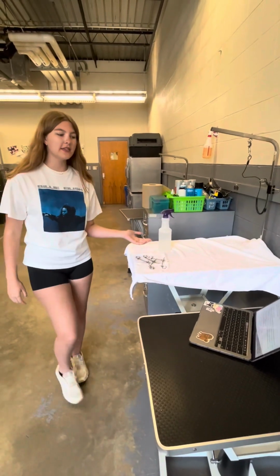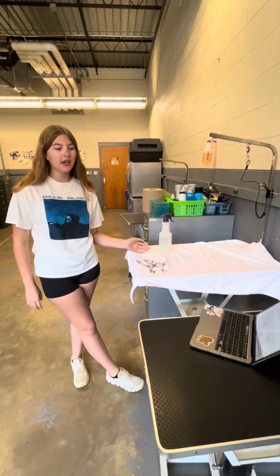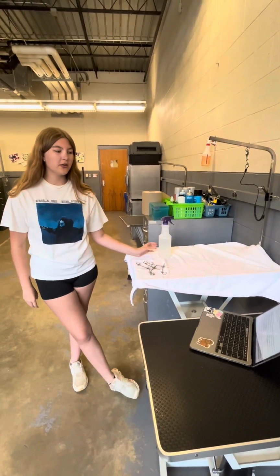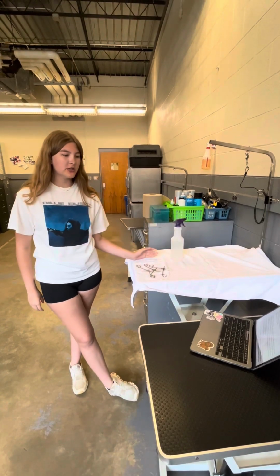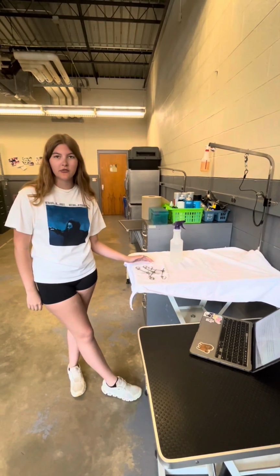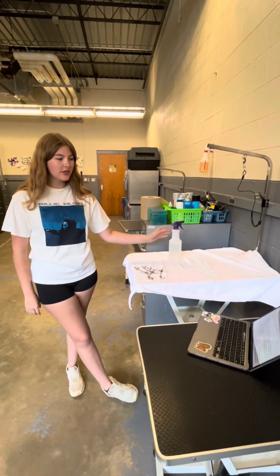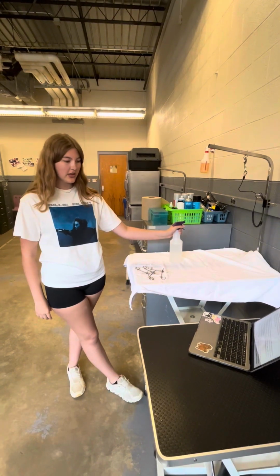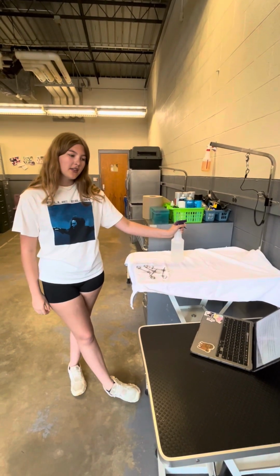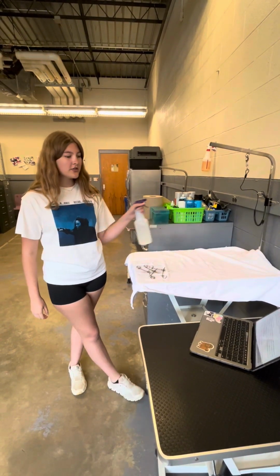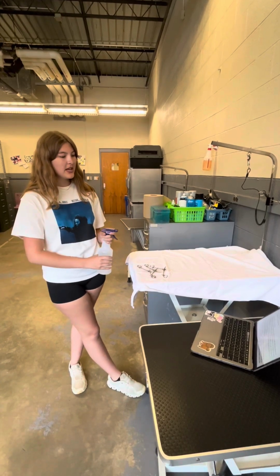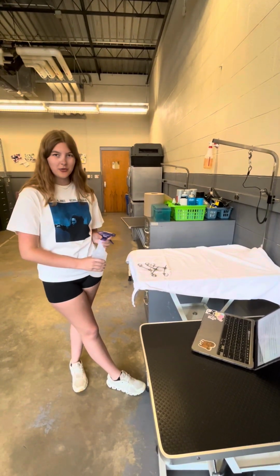Instruments need to soak in a solution called instrument milk. This is a non-oily lubricant that provides the instruments with a protective barrier that helps prevent corrosion. This is especially important for those instruments with hinges or moving parts. There are also spray bottle forms of lubricant that some hospitals use.